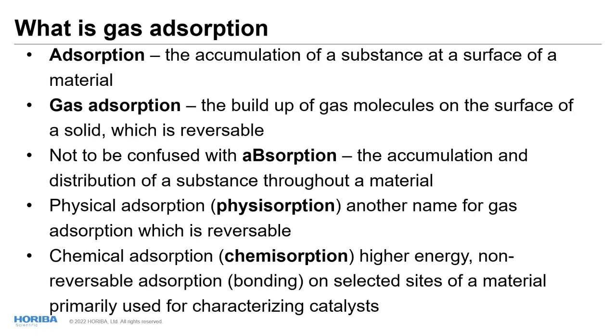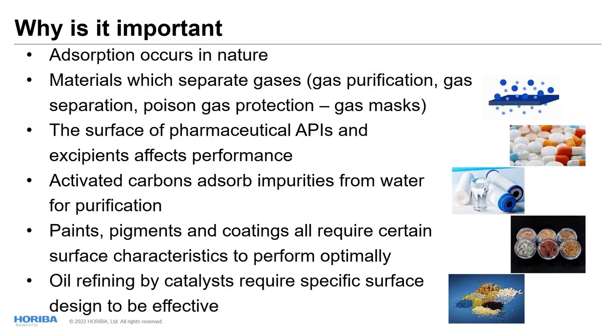Chemical adsorption, or chemisorption, is a much higher energy, non-reversible bonding of gas molecules on selected sites of a material, primarily used for characterizing catalysts. For example, in an oil refinery a catalyst might be platinum metal dispersed on an aluminum support. Physical adsorption would reveal total surface area, but chemisorption would bond gas molecules only to the platinum, allowing us to determine the platinum surface available for reaction.